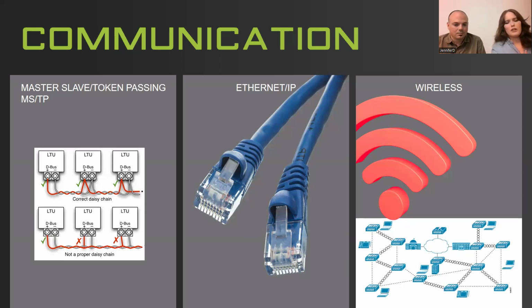The devices themselves are usually more costly, but like I said, labor is less intense. What about building conditions? You've got to keep that in mind on a wireless system. It's going to be really tricky if you try to install a wireless system in a building with very specific materials it's made of. So if you have a very secure site where the walls are made of 5 feet of concrete or very thick metal, that communication is more easily disrupted.